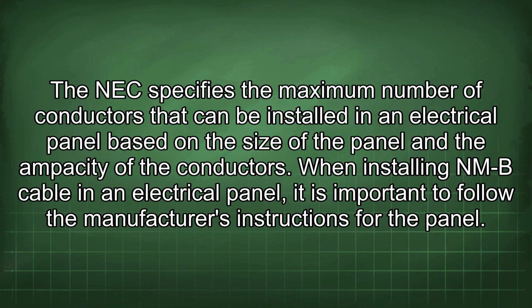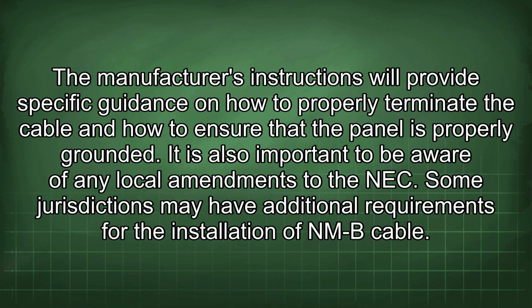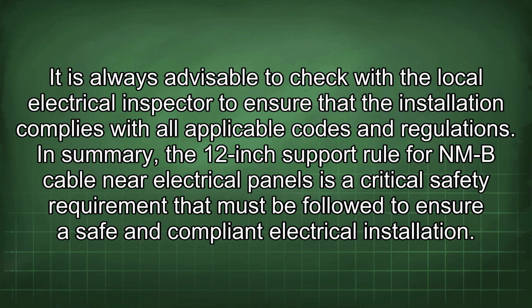When installing NMB cable in an electrical panel, it is important to follow the manufacturer's instructions for the panel. The manufacturer's instructions will provide specific guidance on how to properly terminate the cable and how to ensure that the panel is properly grounded. It is also important to be aware of any local amendments to the NEC. Some jurisdictions may have additional requirements for the installation of NMB cable. It is always advisable to check with the local electrical inspector to ensure that the installation complies with all applicable codes and regulations.